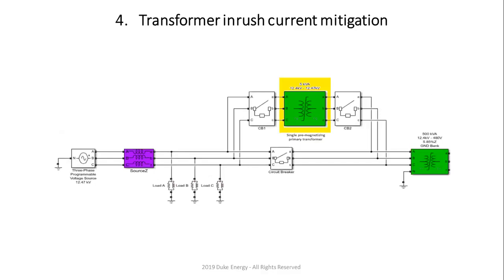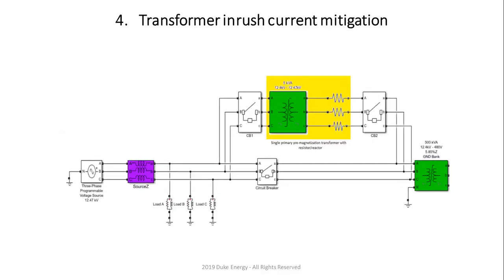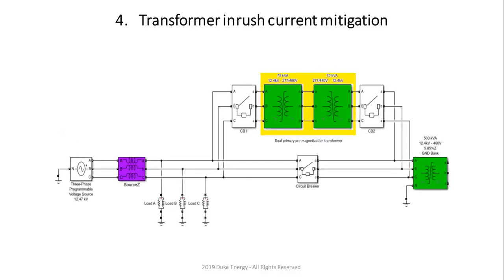Another option we tried was a smaller transformer. You would pre-energize the big transformer by going through the smaller transformer. Some studies have shown that this smaller transformer has to be about 0.5% to 1% of the big transformer, so in this case it would have to be in the range of 5 kVA. The problem is, how do you build a 5 kVA transformer at 1247 to 1247? It is physically impossible, so this wasn't the case. So we tried to do the same by adding a resistor or reactor, because as you know, adding a resistor or reactor to the circuit reduces the current going in. But the 5 kVA transformer is what got us out of that option. So this is one of the options that we have done.